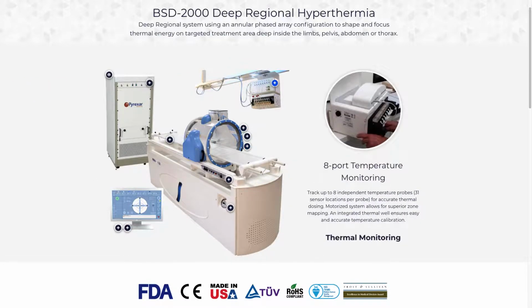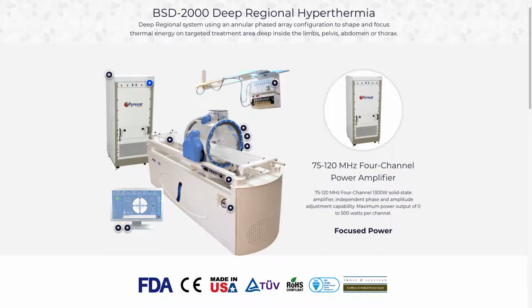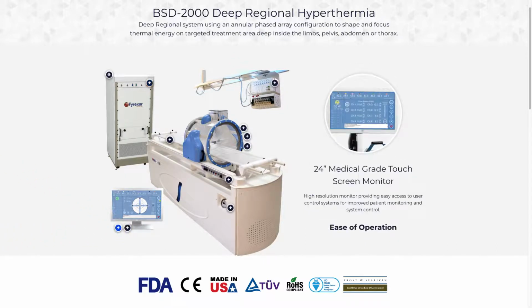Mounted overhead, the temperature probe system with a motorized driver to allow for temperature mapping using up to 8 probes. The temperature box has an integrated thermal well for easy and accurate temperature calibration. Powering the system is a 4-channel 1300 watt solid-state amplifier with independent phase and amplitude adjustment capability. Maximum power output is 500 watts per channel. And the computer control system is housed in a 24-inch medical-grade touchscreen PC with embedded Windows operating system.